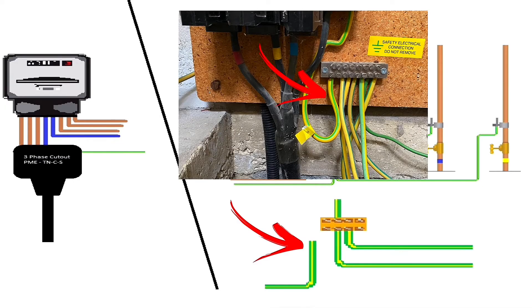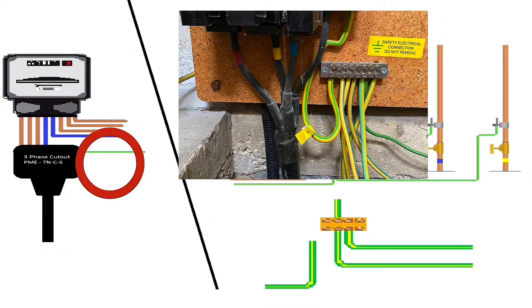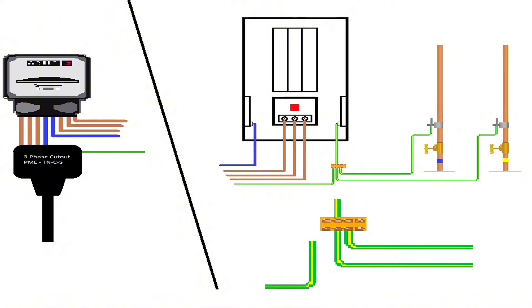You disconnect the 16mm, or whatever size it is, earthing conductor, as I've shown there, which is the incoming one from the main supply. With that disconnected, remembering the board needs to be isolated before disconnecting it, we can now test.